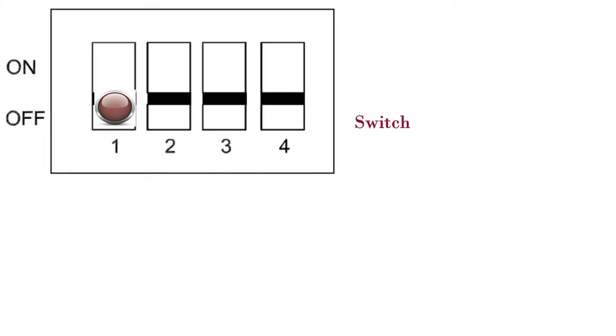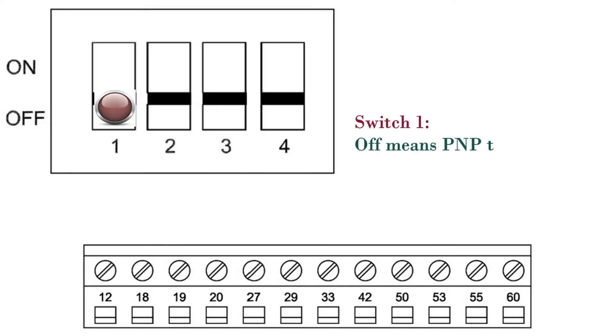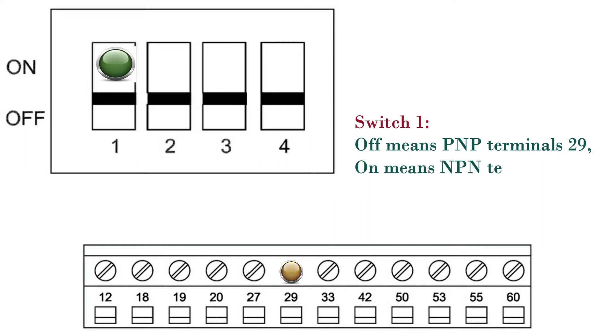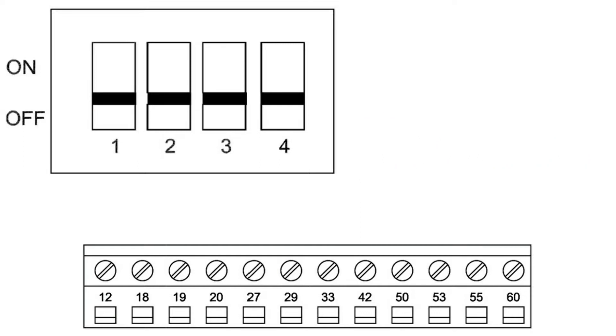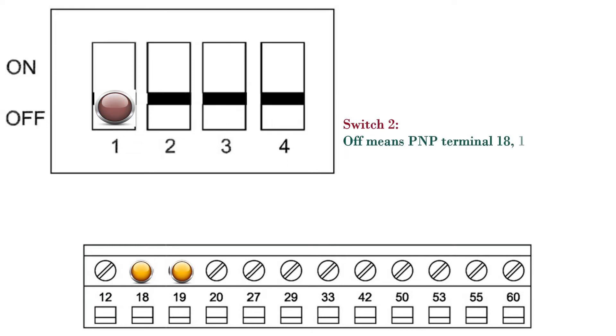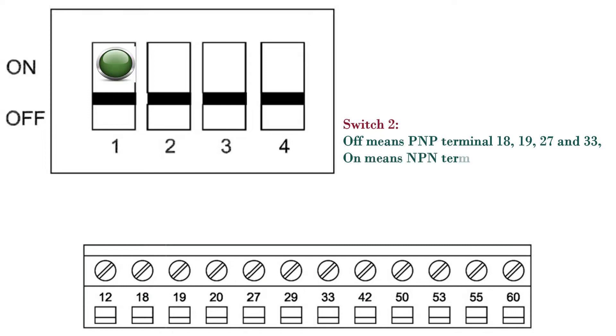Switch 1: Off means PNP terminal 29; On means NPN terminal 29. Switch 2: Off means PNP terminals 18, 19, 27 and 33; On means NPN terminals 18, 19, 27 and 33.